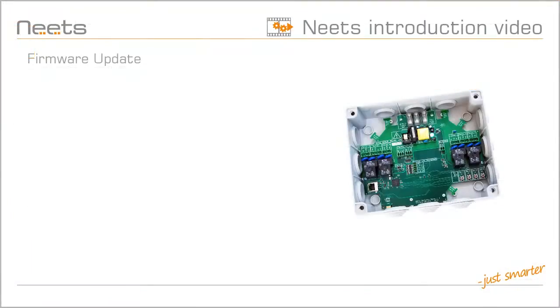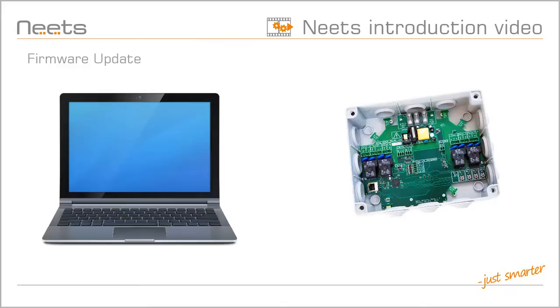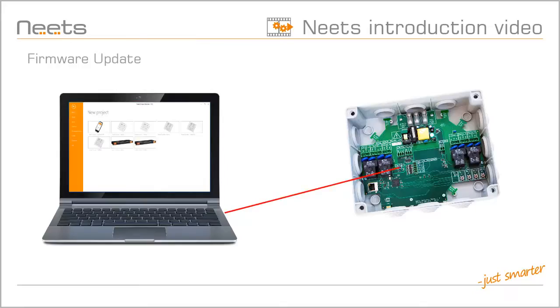For the automatic configuration to work, it is important that you update your Neets Switching Relay 4 with the latest firmware. It is simple to do: connect the Switching Relay to your PC via USB and open up the Project Designer. The Project Designer will detect the relay and prompt you to update the firmware. Click OK and the latest firmware is uploaded to the relay box.